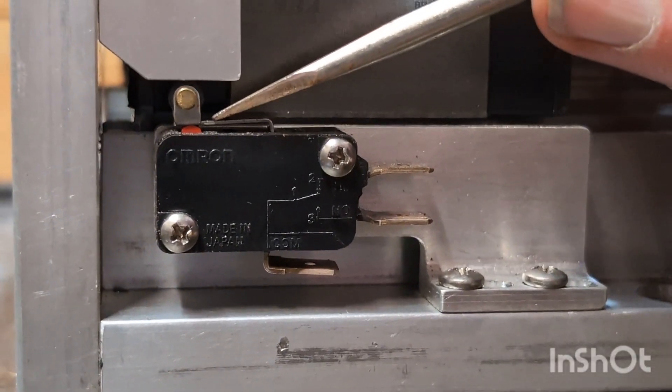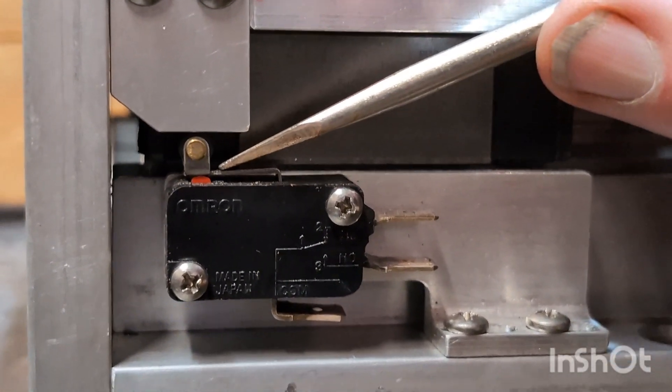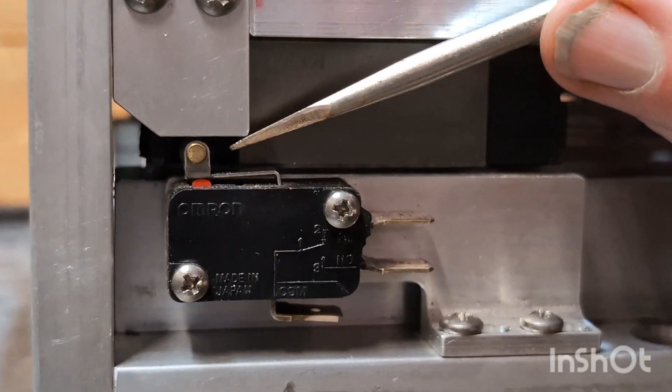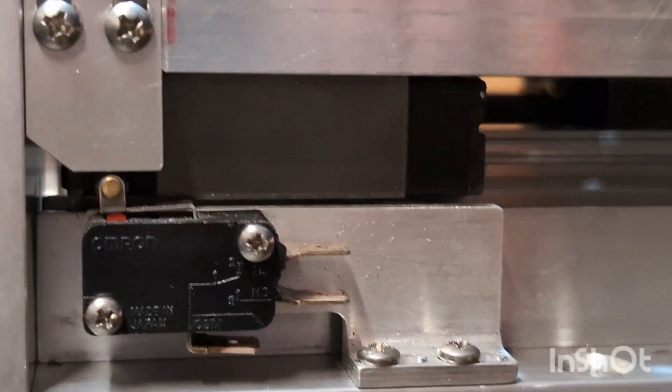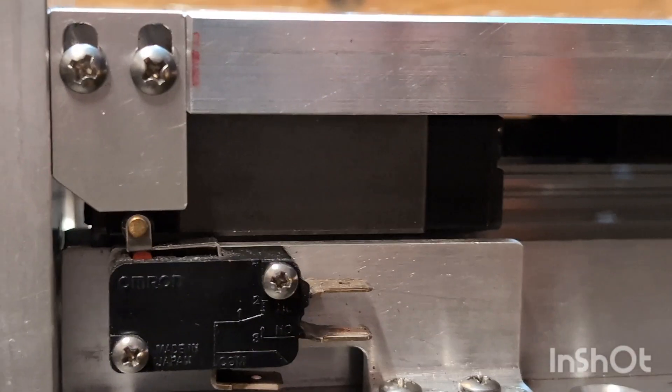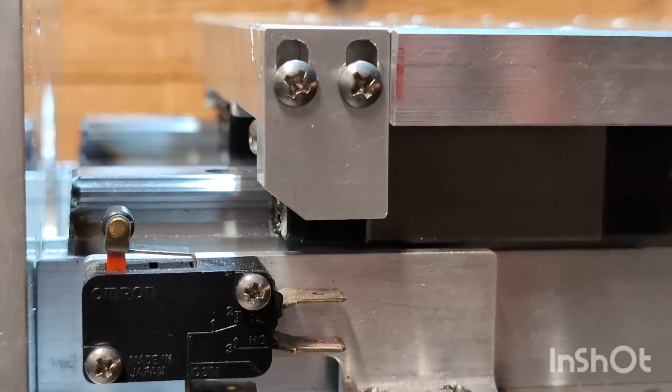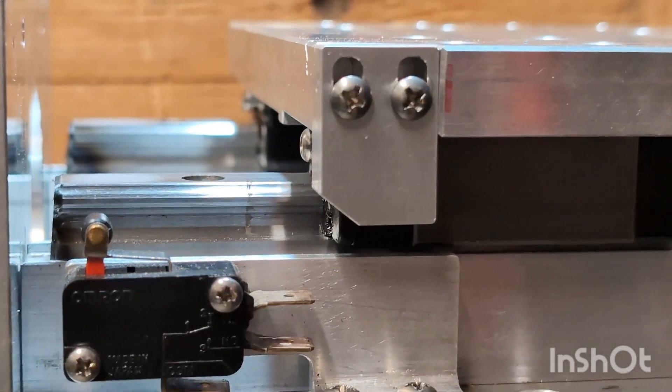If I go past that limit switch in, let's say, a runaway condition, nothing happens. I can do this all day long, no problem. Now if you've got a proximity switch, same thing.